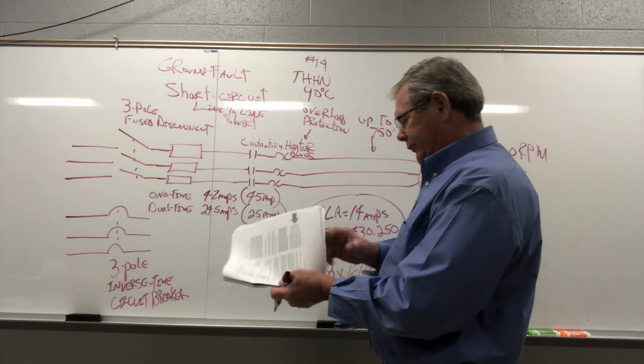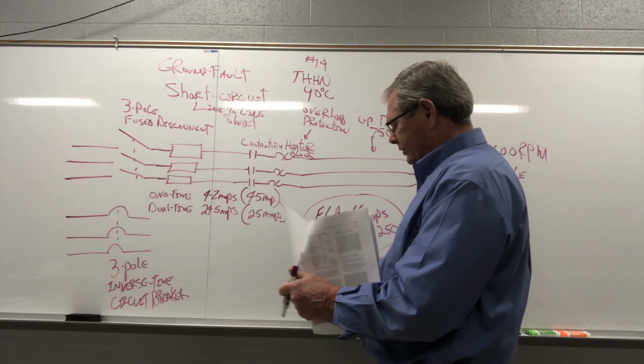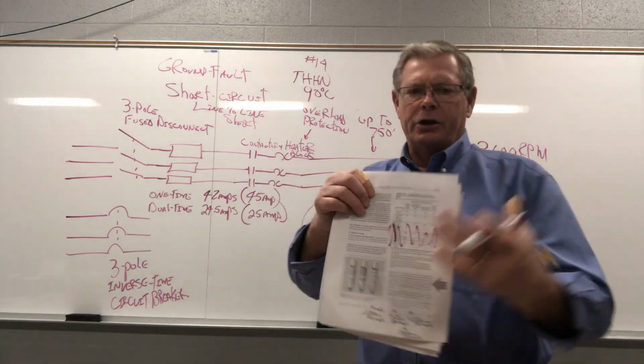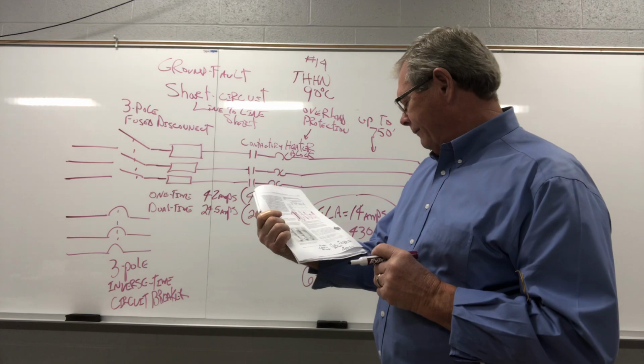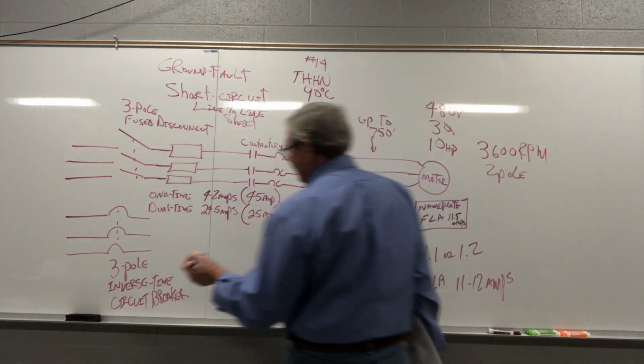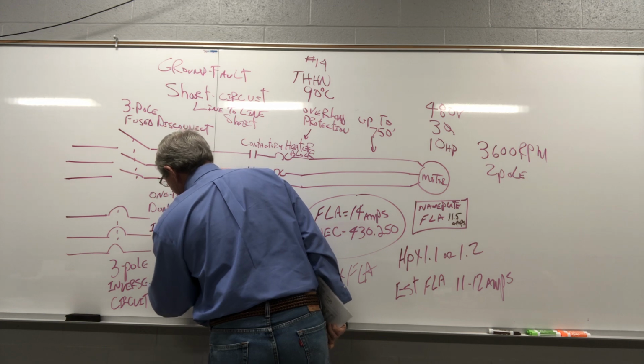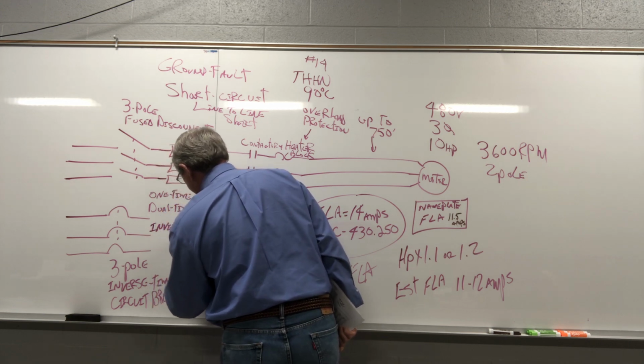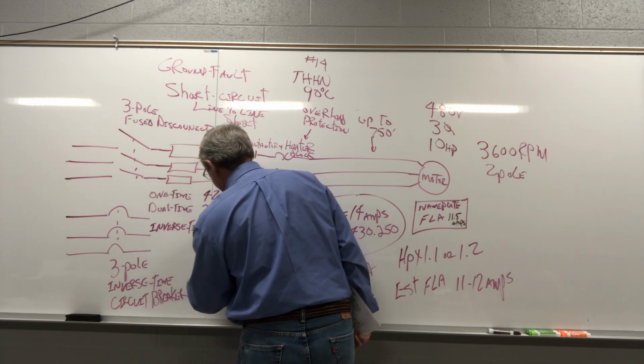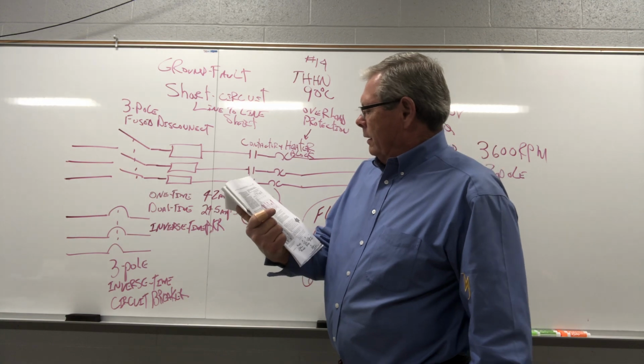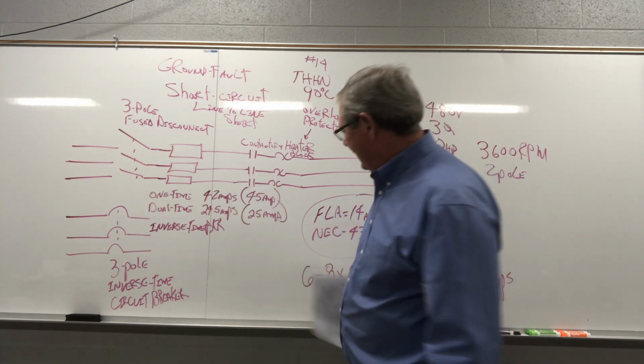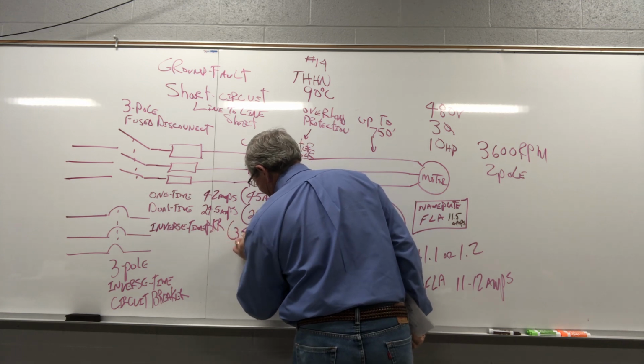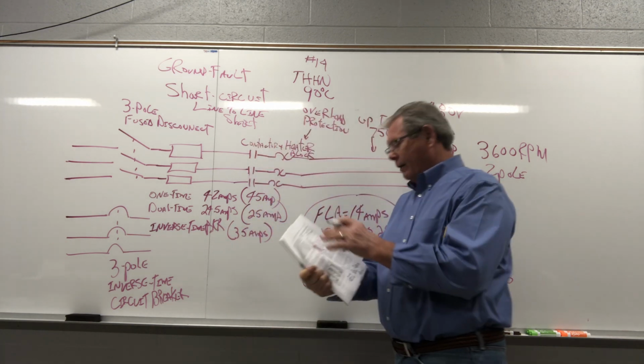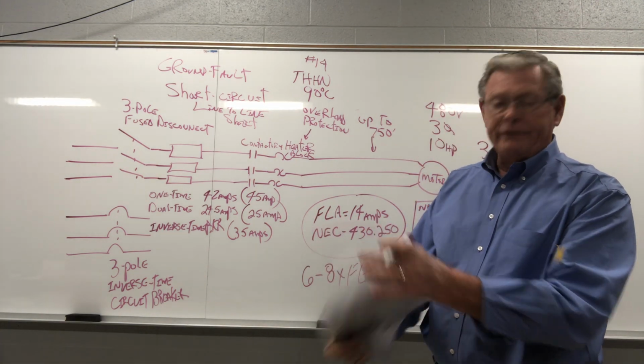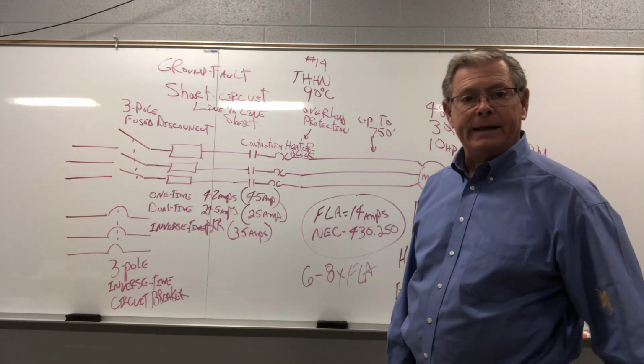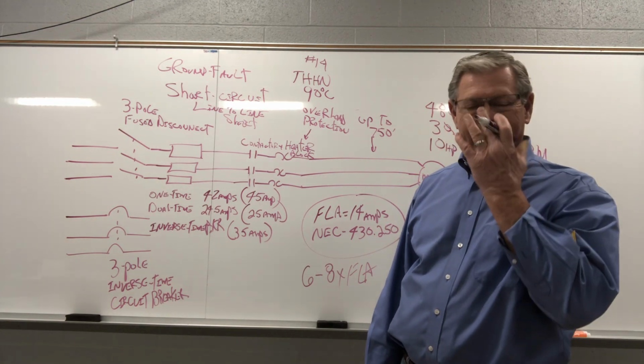Okay, so a circuit breaker has a multiplier, inverse time circuit breaker, and it's on this chart here, of 250%. And 250%, okay, let me write this down, inverse time breaker. So 250% times 14 is 35 amps. Now, if we look over on the next page, 35 amps is a standard size breaker, so we don't need anything else. We put a 35 amp breaker in there, we're good to go.